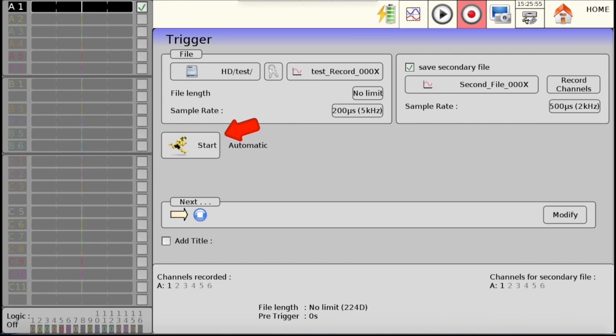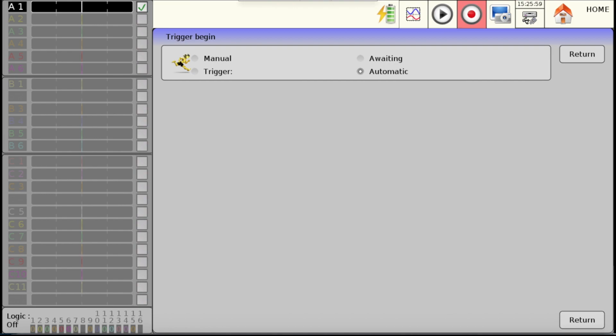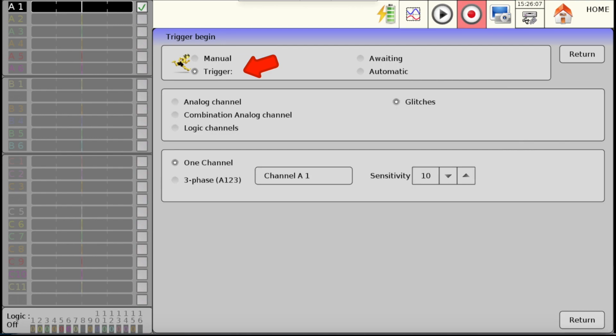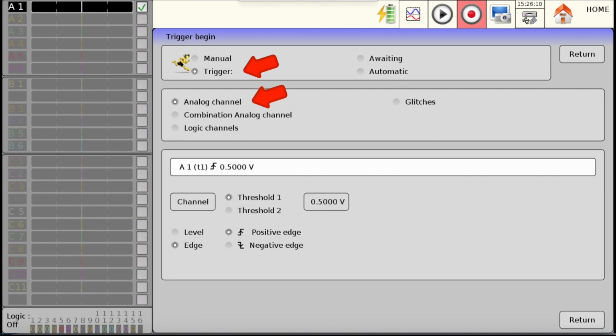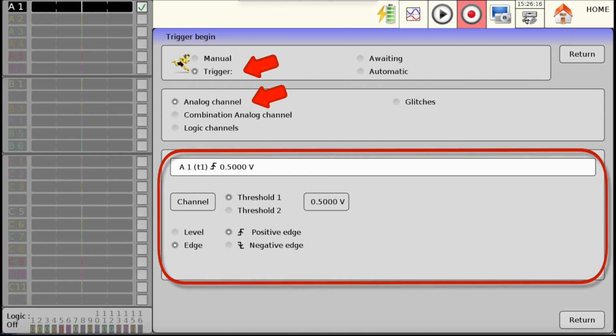To set a trigger correctly, a start condition and a stop condition must be defined. The manual trigger will wait for you to press start and stop to start and stop the recording. The analog channel trigger will wait for the condition defined on the analog channel selected to be achieved. Trigger on a positive or negative edge or a level.